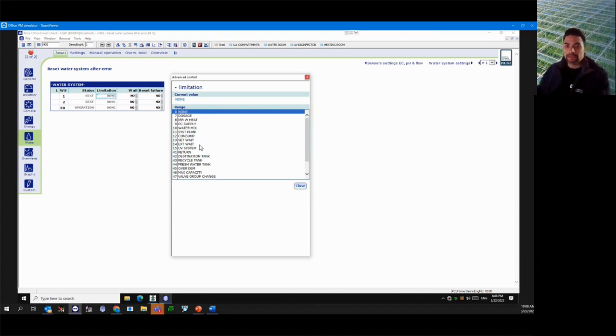So either the mixing tank went dry, so you have to find out, okay, why did the mixing tank go dry? Let's say there's a fill pump filling that mixing tank, maybe something's wrong with that, or the supply line, something's going on with that. The overload just needs to be reset inside a Priva water system panel. There will be an overload with a dial on it that needs to be reset, or it could be a temperature switch.